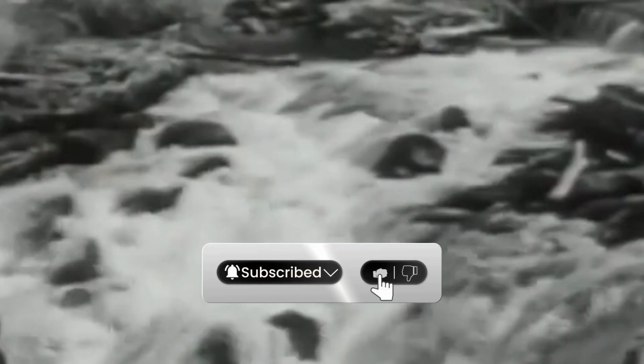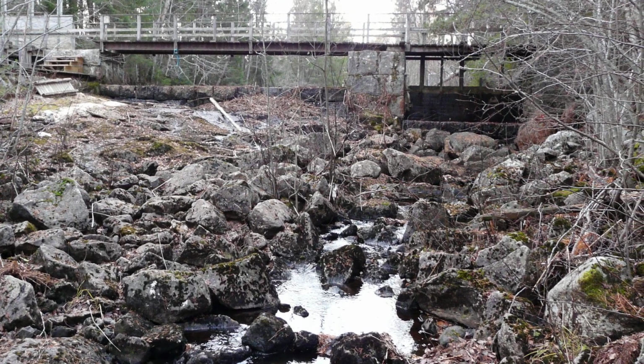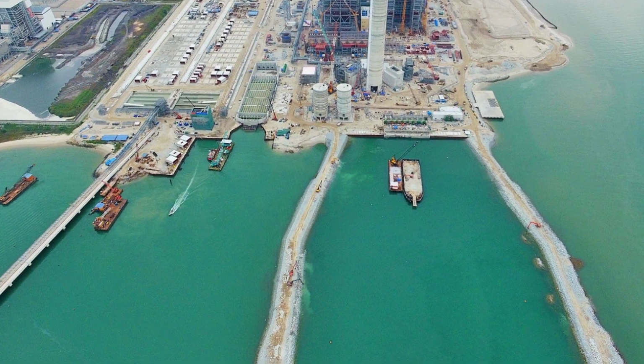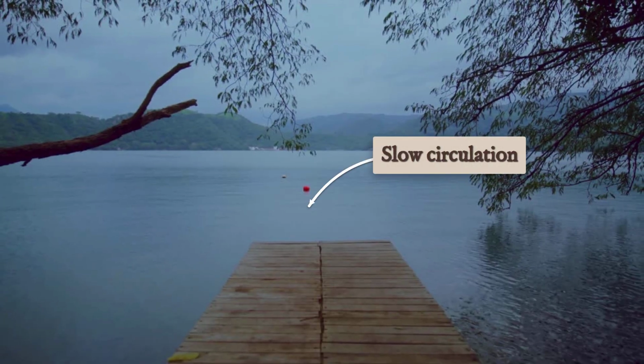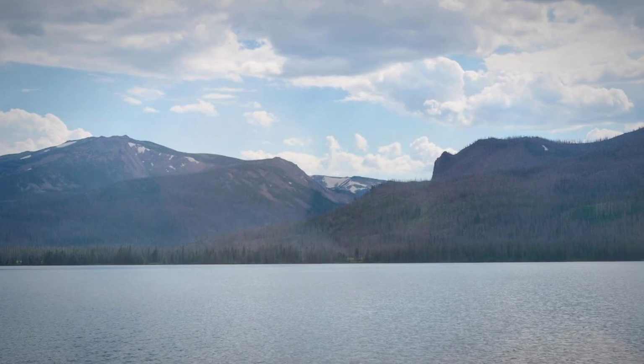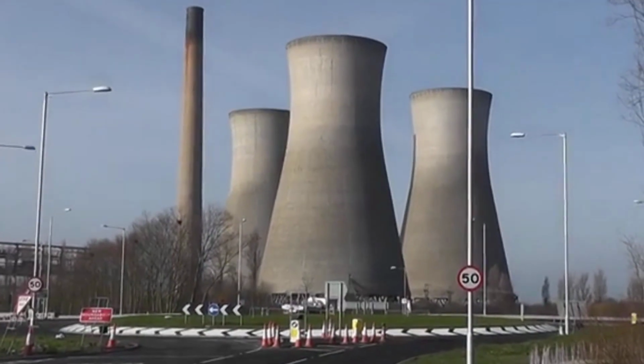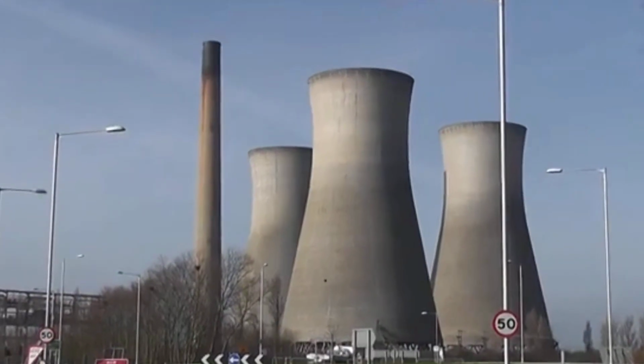One straightforward option is to utilize an existing cooler water source, such as a river, lake, or sea. Many power plants, for example, draw water from a lake, circulate it through condensers, and then release it into a channel where it slowly circulates back to the lake's opposite side. This slow circulation allows the water to cool before returning to the plant. However, not every thermal power plant has access to a suitable lake or river for cooling, and there are environmental impacts from heat discharge and water intakes that require careful consideration. Consequently, many power plants employ cooling towers instead.